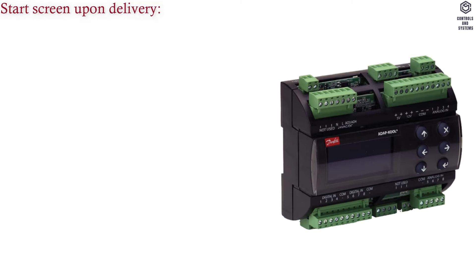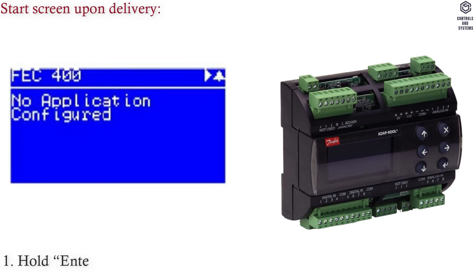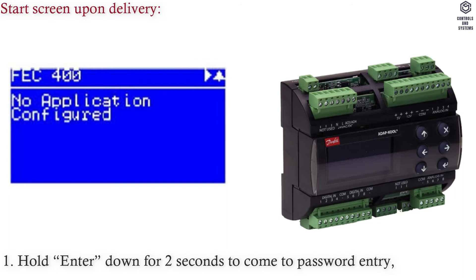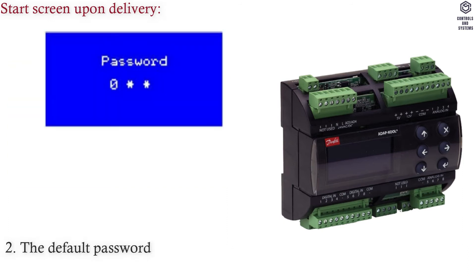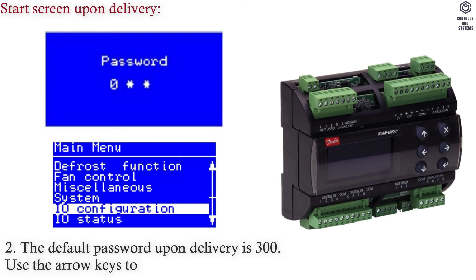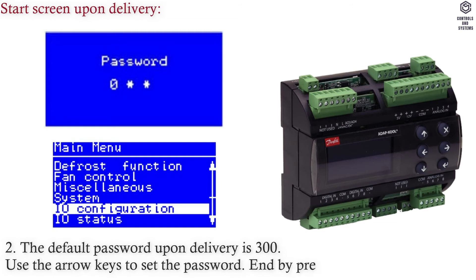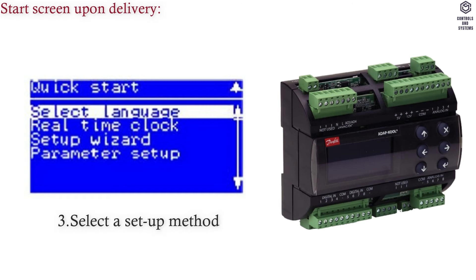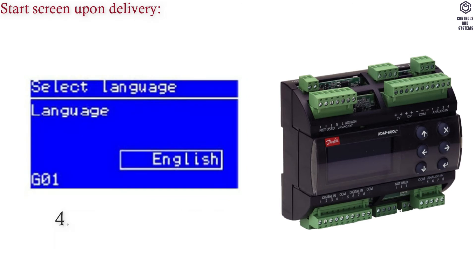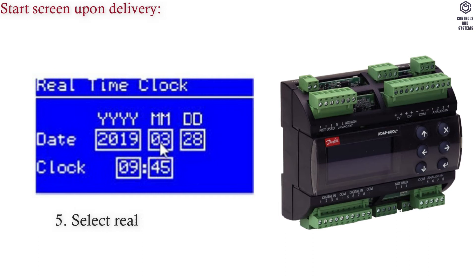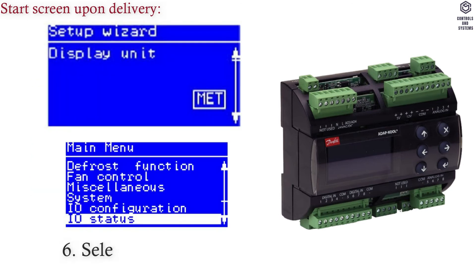Start screen upon delivery: (1) hold Enter down for 2 seconds to come to password entry; (2) the default password upon delivery is 300 — use the arrow keys to set the password and press Enter; (3) select a setup method and press Enter; (4) select language; (5) select real-time clock; (6) select display unit.